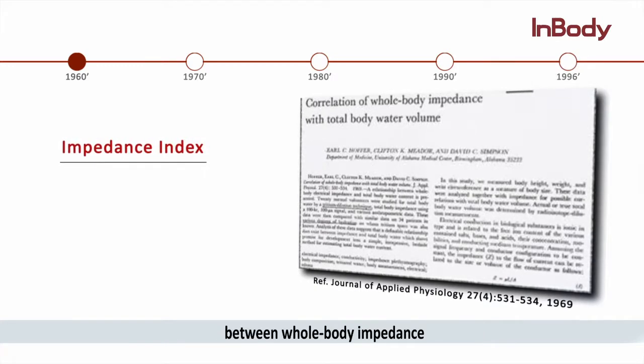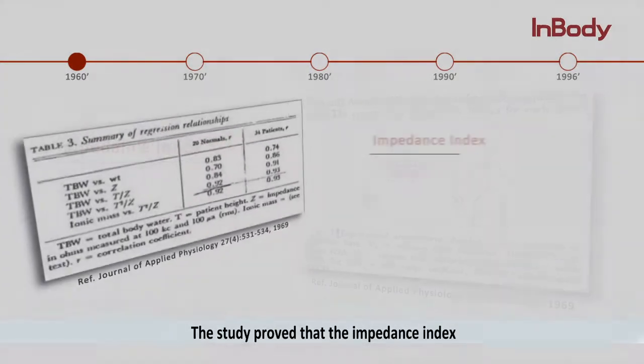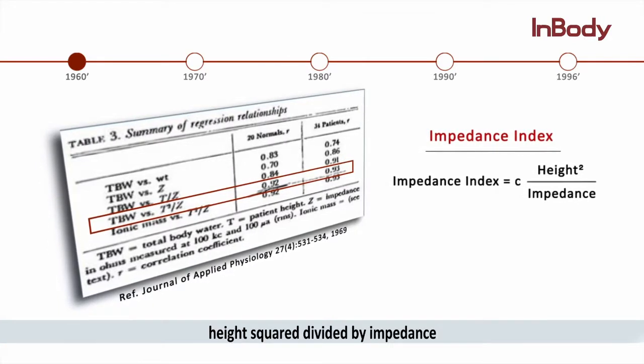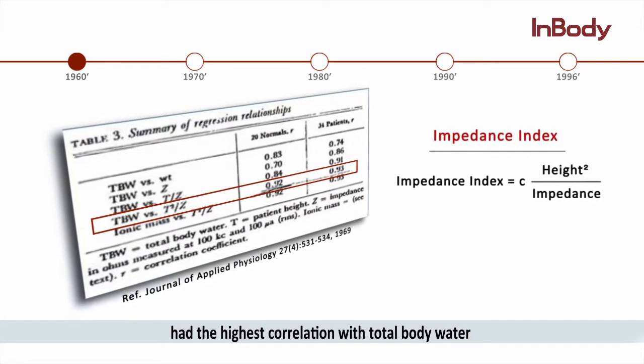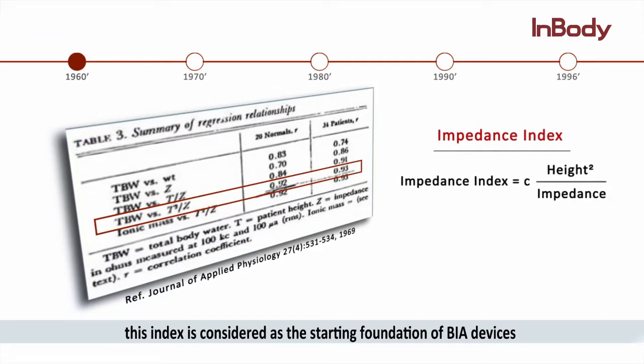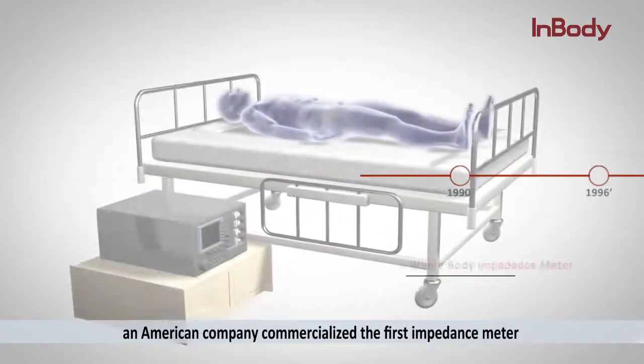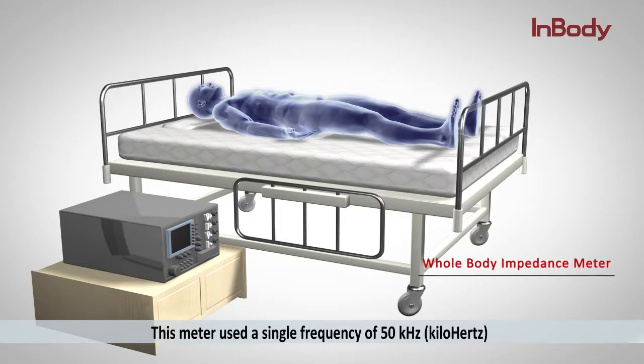In 1969, an experiment was carried out to find the correlation between whole-body impedance and volume of total body water. This study proved that the impedance index — height squared divided by impedance — had the highest correlation with total body water, and is considered the starting foundation of BIA devices. Ten years later, an American company commercialized the first impedance meter, which used a single frequency of 50 kilohertz.